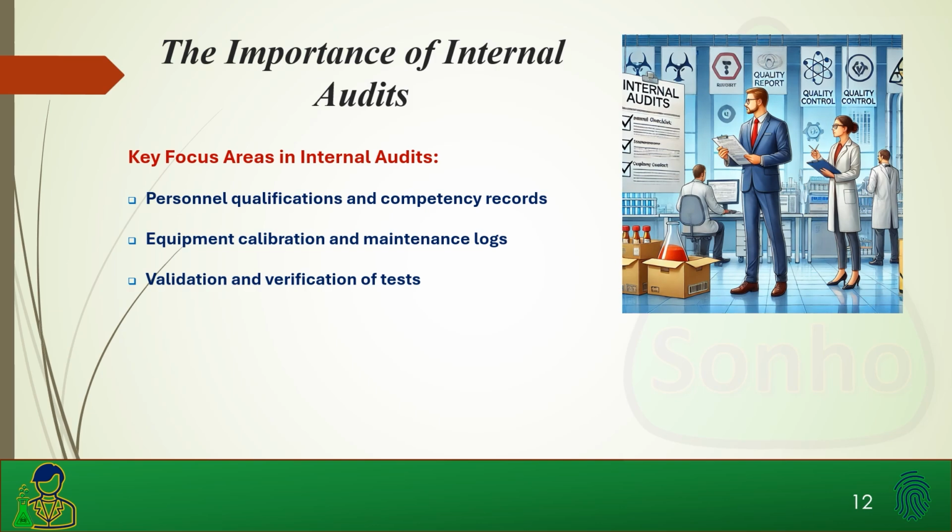Quality control and quality assurance practices. The daily quality control should be run, and it should be documented using either LJ charts, Levey-Jennings, or some other tracking metric, as well as your quality assurance. However you do your quality assurance, I prefer to do monthly quality assurance, but some laboratories do quarterly. However your laboratory documents quality assurance, it is important to make sure that during the internal audit these practices are being accomplished. These are all things that can easily fall behind and fall to the wayside.